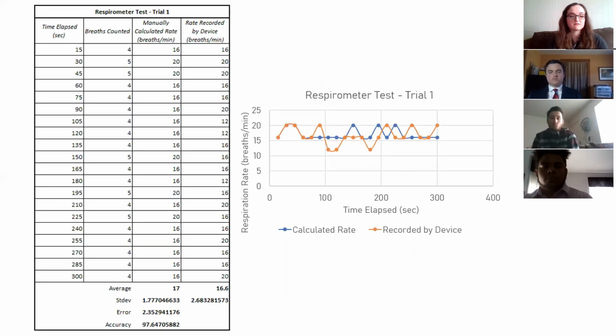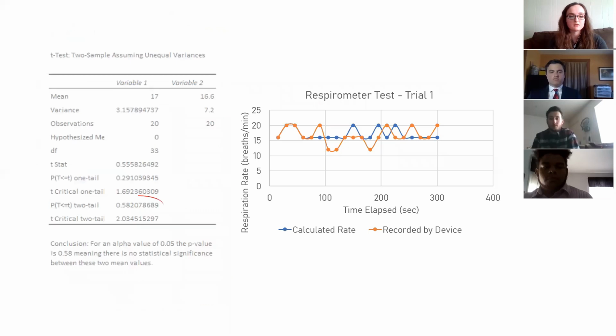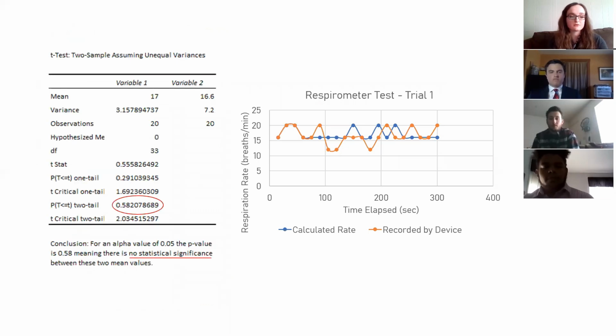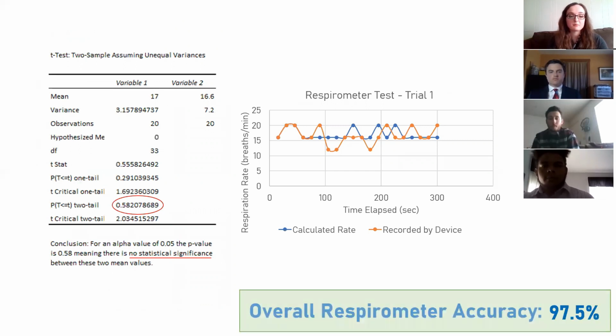To determine the accuracy of the device, the calculated rate was compared to breaths counted manually over the same 15-second interval, and this was done for a total of 5 minutes. The average rates were compared using a two-tailed t-test, as shown here. And as we can see, the statistical analysis of this data shows that there's no significant difference between the device and our manual method. So we are able to say that our device is capable of detecting respiration. Overall, this test was repeated 3 times, and the overall accuracy was determined to be 97.5%, which is well above the specification that we were required to meet.